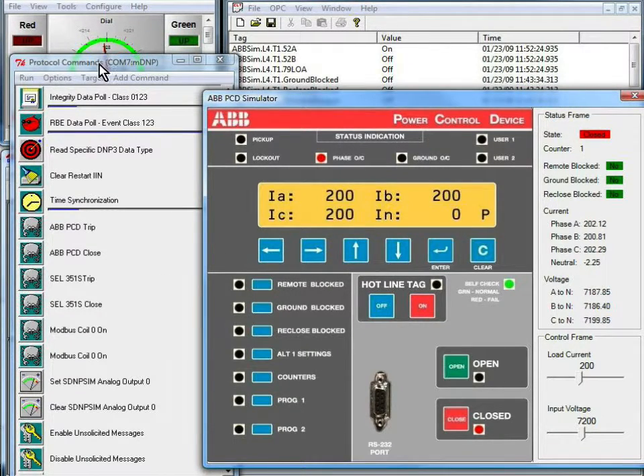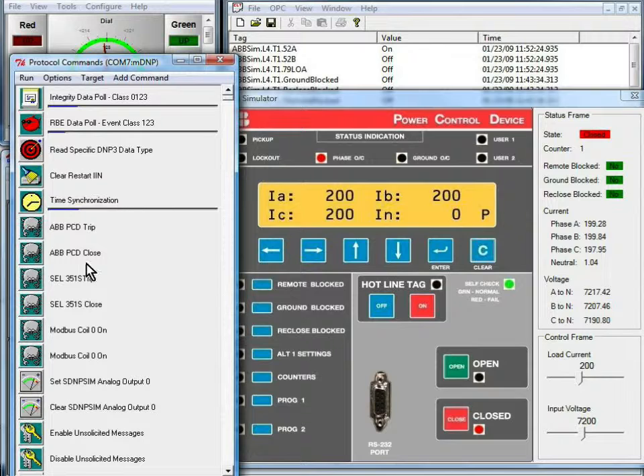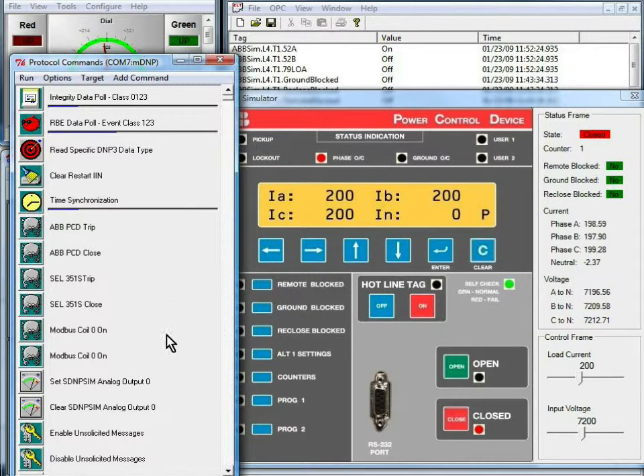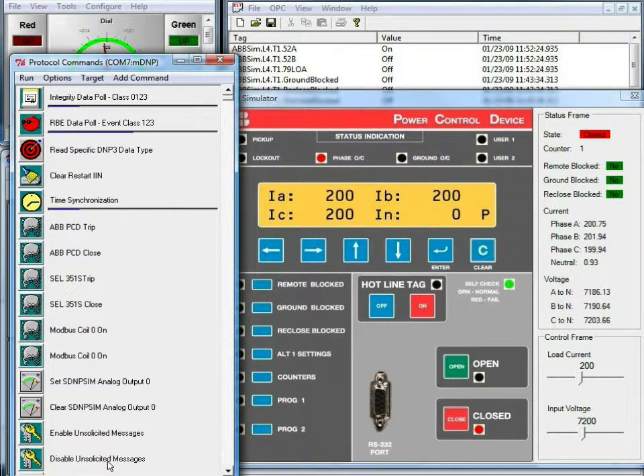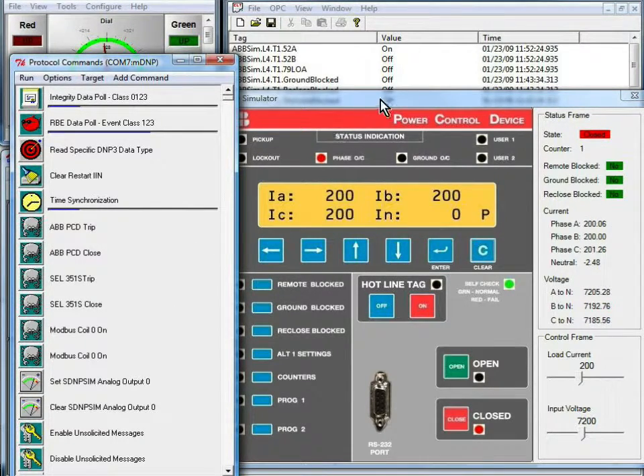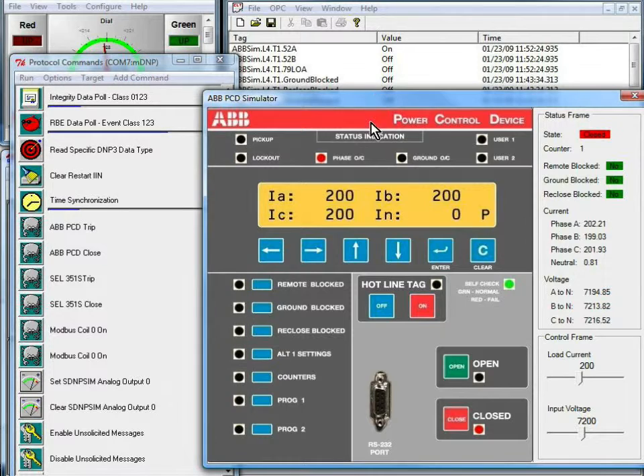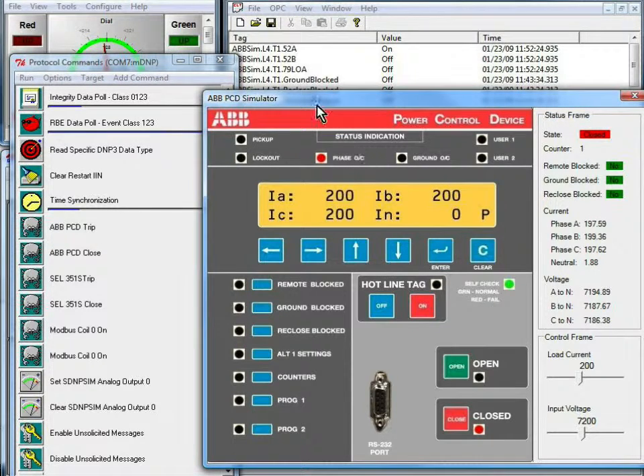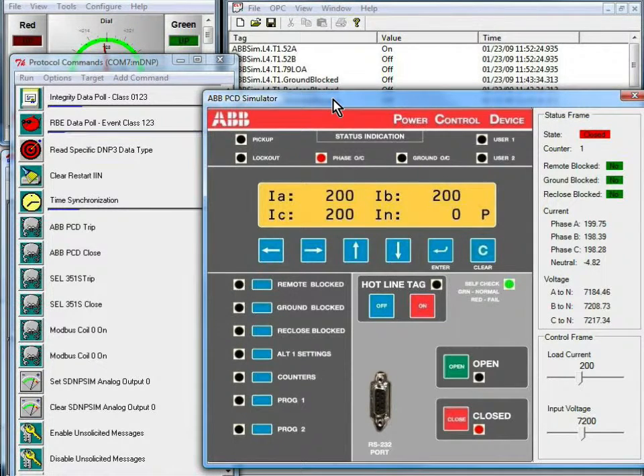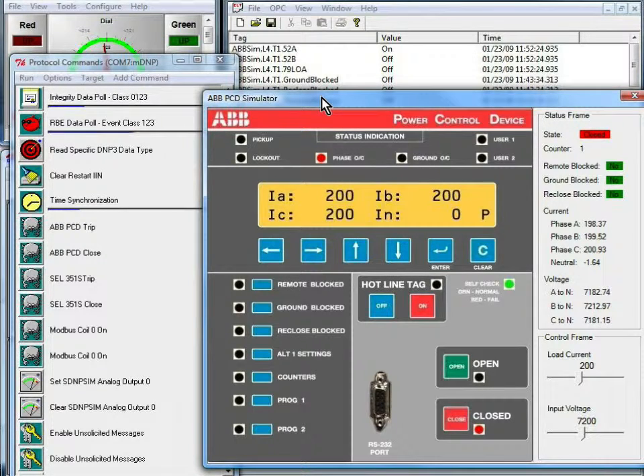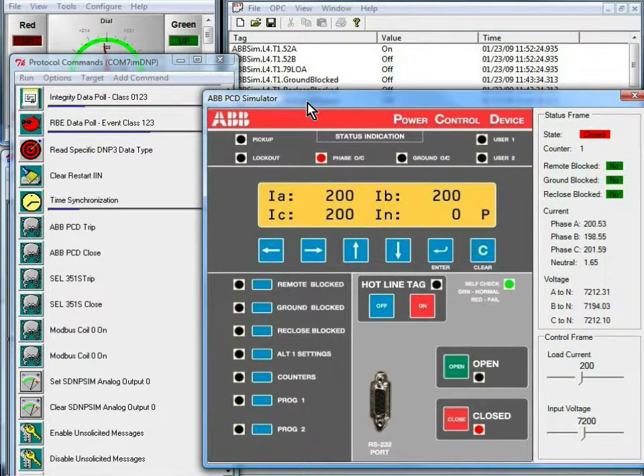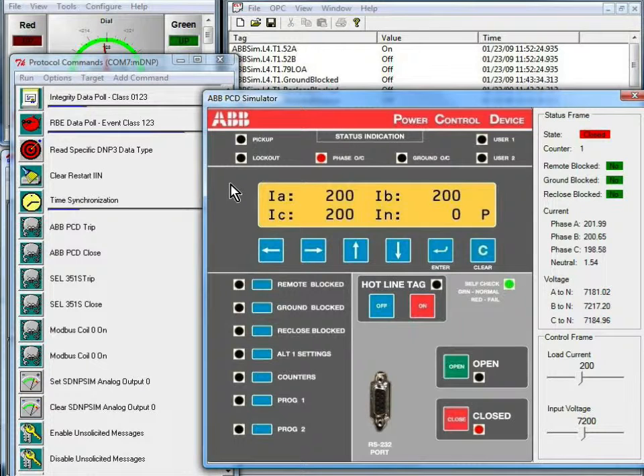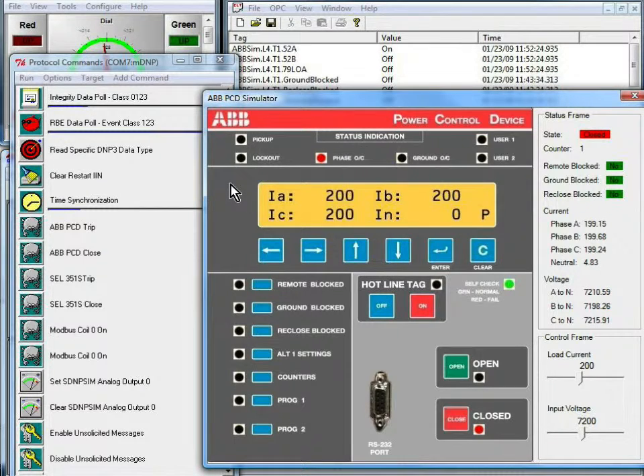Here, this master DNP simulator communicates to the SCADA data gateway via serial connection, and the PCD simulator is communicating to the SCADA data gateway through a TCP IP connection. So we're seeing the gateway used as a data concentrator and also translating from a serial to a TCP IP connection.